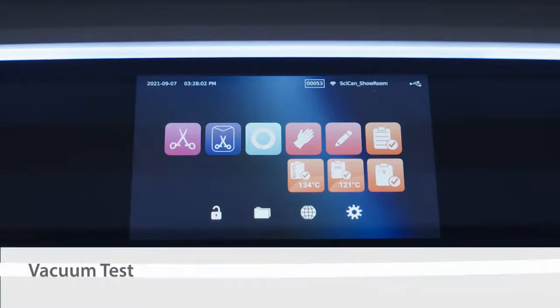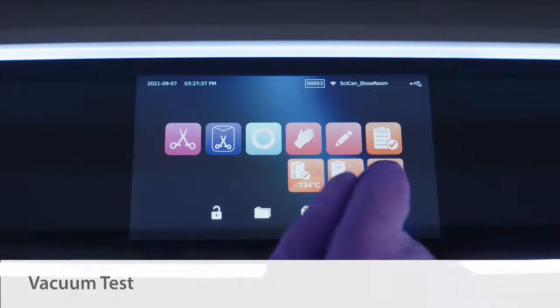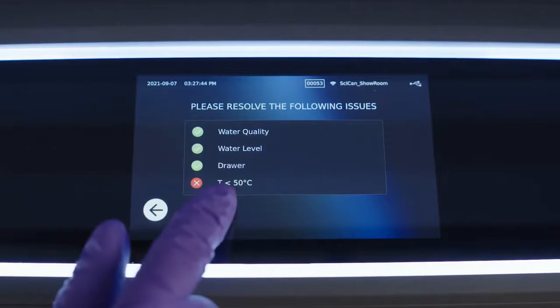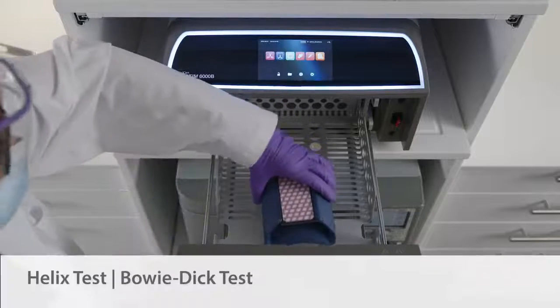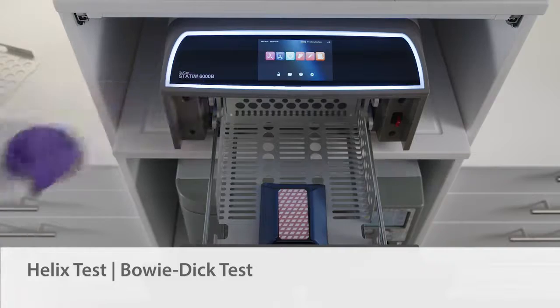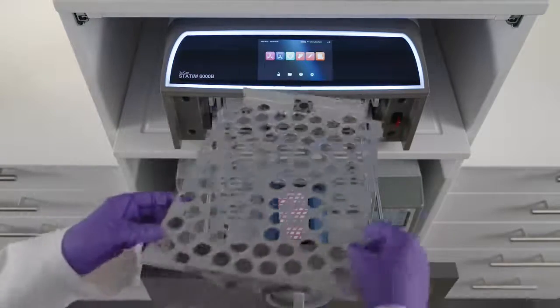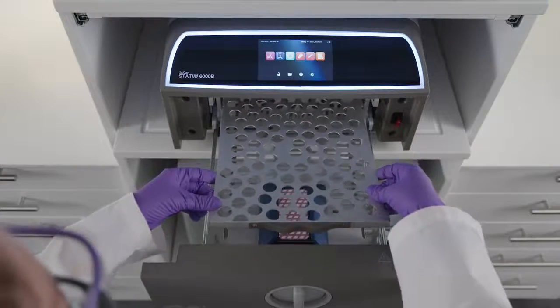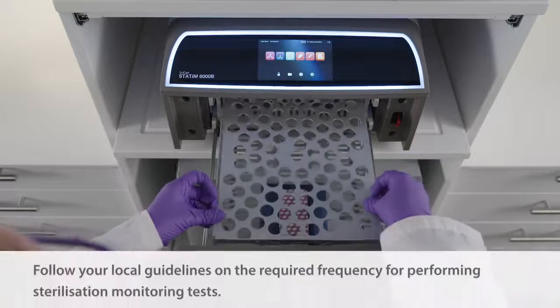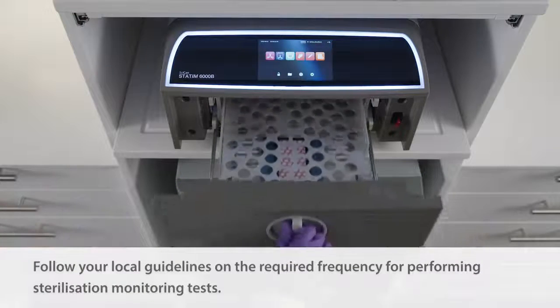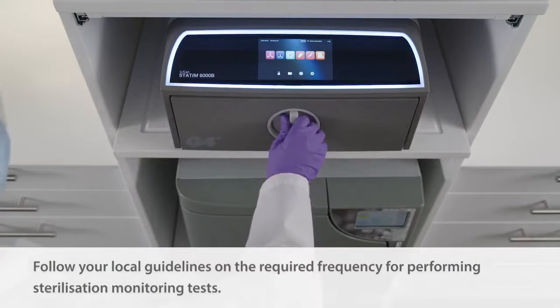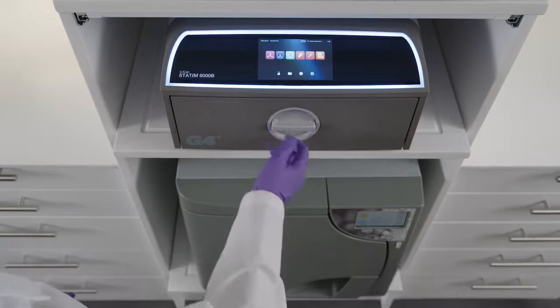A vacuum test, which needs to be completed with a cold chamber, as well as helix and Bowie-Dick tests. These are done in a warm chamber with the test packs placed on the tray. Follow your local guidelines on the required frequency for performing sterilization monitoring tests.